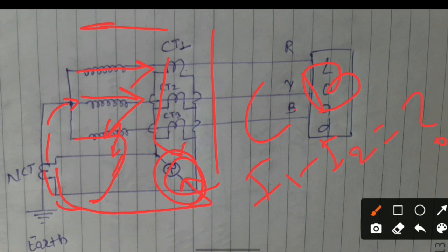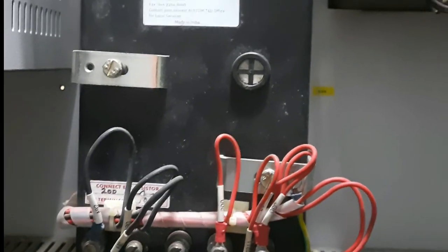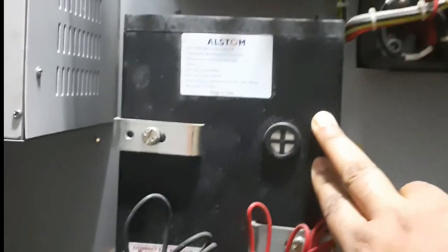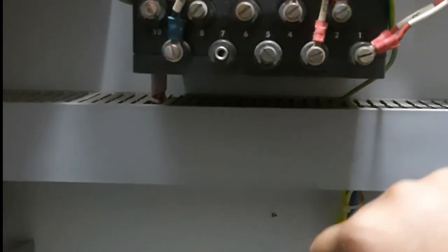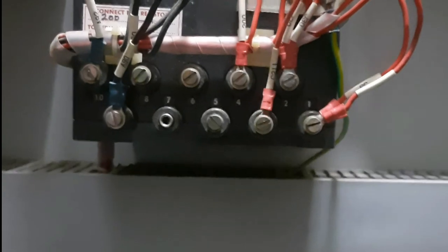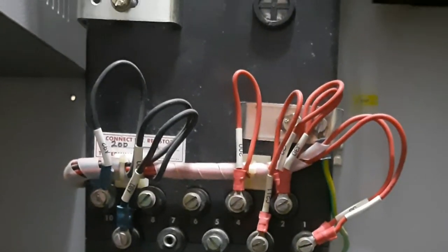Now we are seeing the restricted earth fault relay from the back. Port numbers 1 and 2 go to the annunciator. Port numbers 3 and 4 go to the master trip relay. Ports 9 and 10 receive connections from the CTs. This is the earth wire. In this way we do the connection of the earth fault relay.